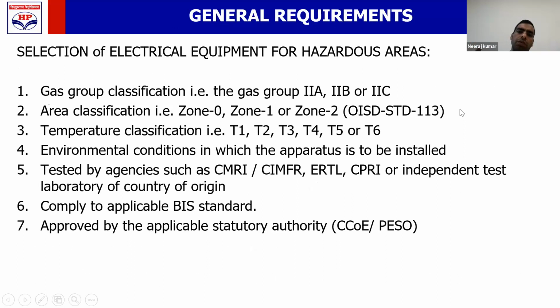The general requirement for electrical equipment in hazardous area. If you are using electrical equipment in a hazardous area, you should see 7 things before selecting it for that area. What are they? The equipment should be suitable to the gas group, suitable to the zone, suitable to the temperature class, suitable to the environment condition of that installation. That installation may be a high temperature installation. Your equipment may not fit there.